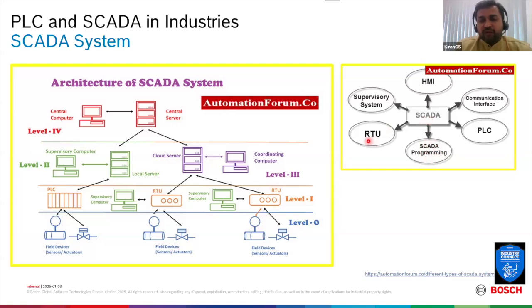Send the signal back to the PLCs, or get the data from the PLC for further processing. This would be the typical use case of any SCADA programming. Likewise, you have RTU, what we call the remote terminal unit, as simple as a temperature controller, and obviously a supervisory system from a software solution angle. If this is a system from an architecture context, typically this is the fourth generation architecture. There are previous architectures also, a run-through I can give.